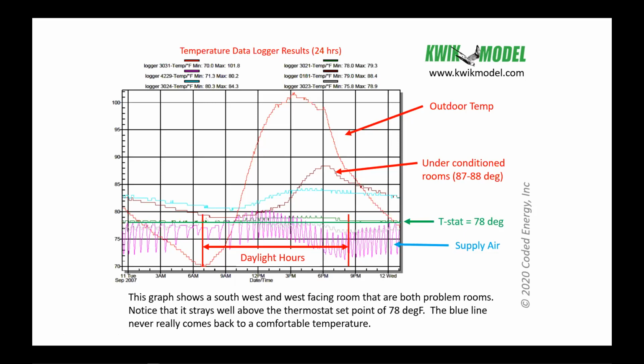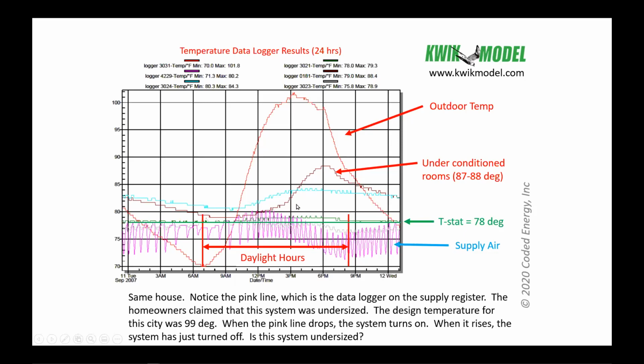The rooms that are not getting the proper airflow get worse and worse. Even if the airflow was lower than it was supposed to be, had the system run for a long period of time, you would not get this spike, because it would go up and it would stay. It would hit a few degrees above the set temperature and stay there. It wouldn't keep rising. So that's a classic example of an oversized air conditioner, and that's what you get. That's very common. Now, this was a very dry climate.